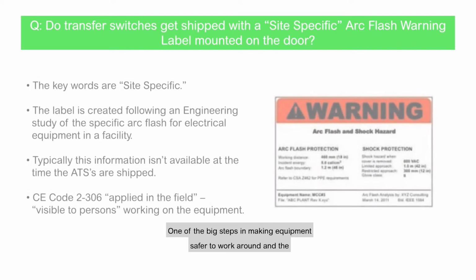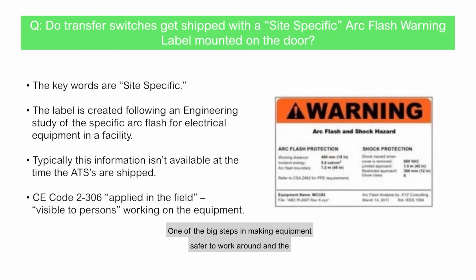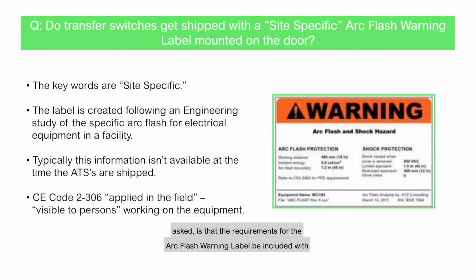One of the big steps in making equipment safer to work around, and the installations safer, was requiring equipment to be labeled with clear guidelines as to the level of hazard. That takes into account both the arc flash protection zone required and the exposure to shock present when working around the equipment. The key thing we're often asked is whether the requirements for the arc flash warning label be included with the equipment.